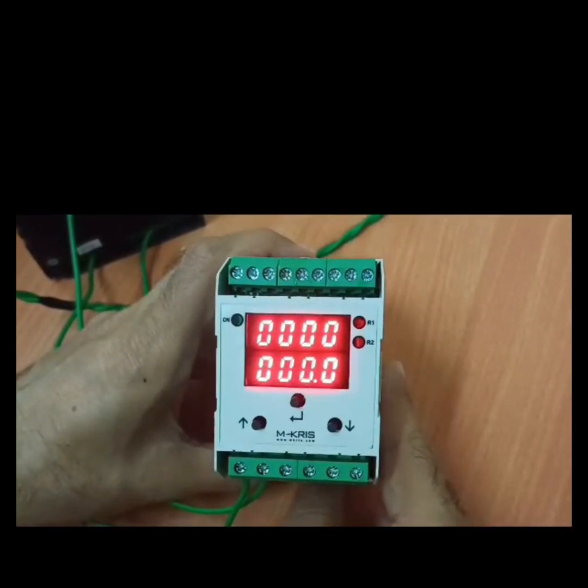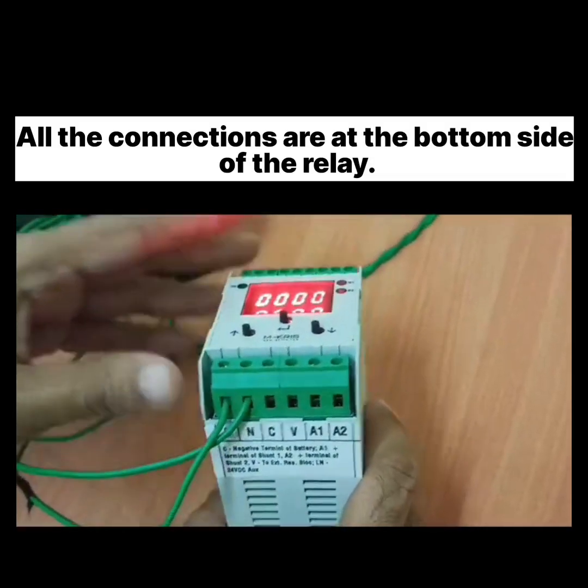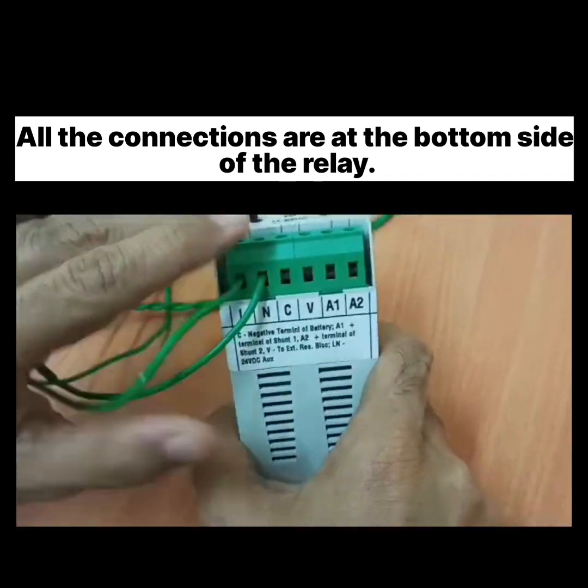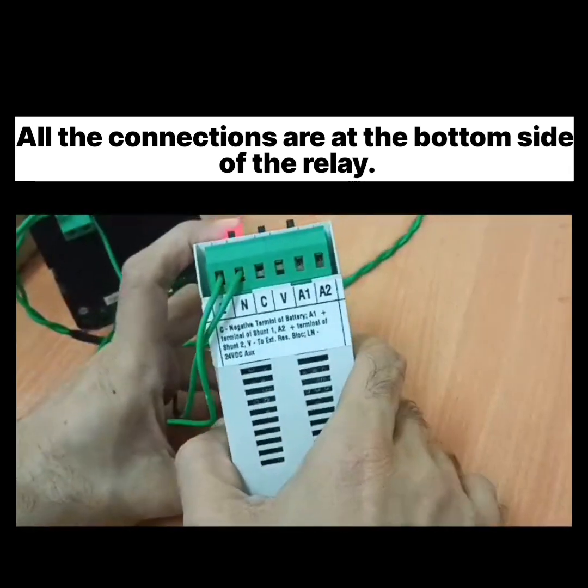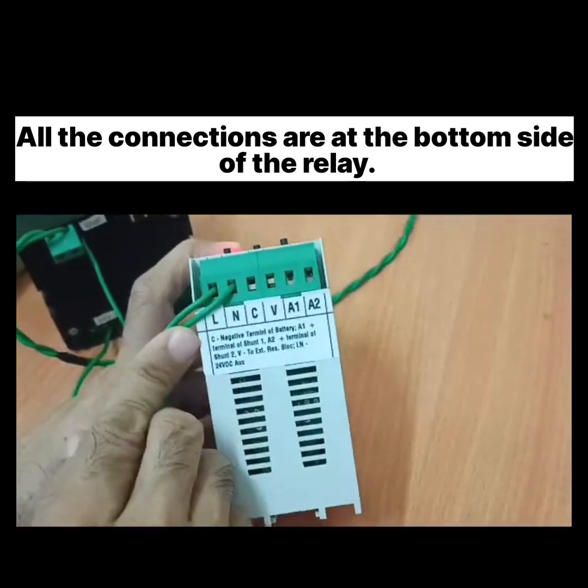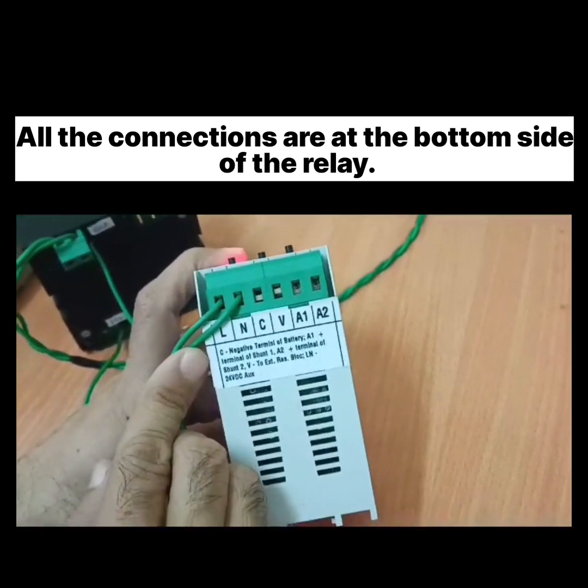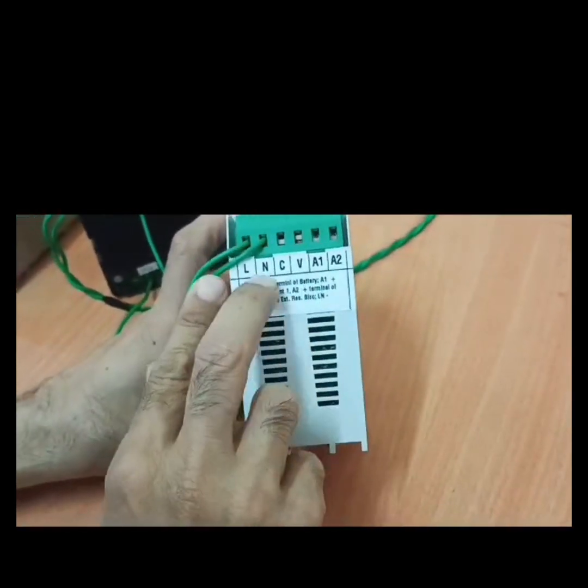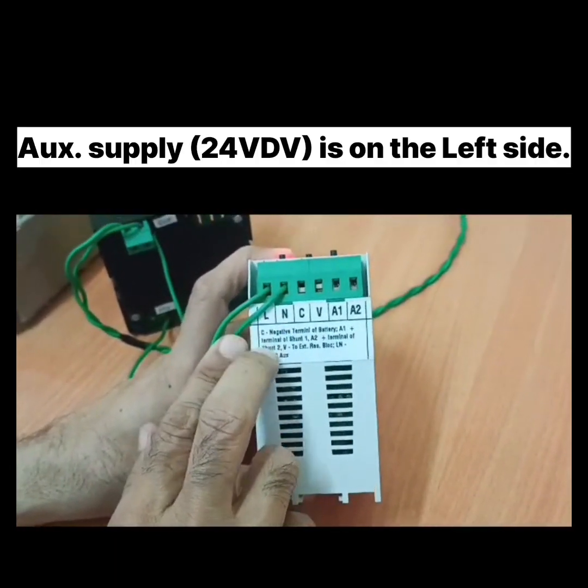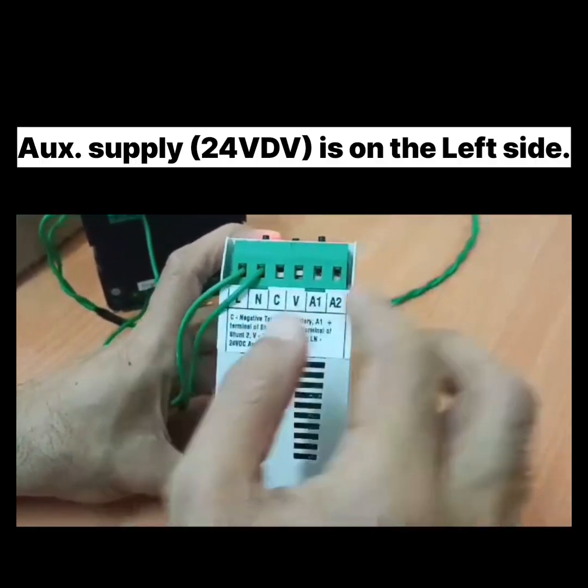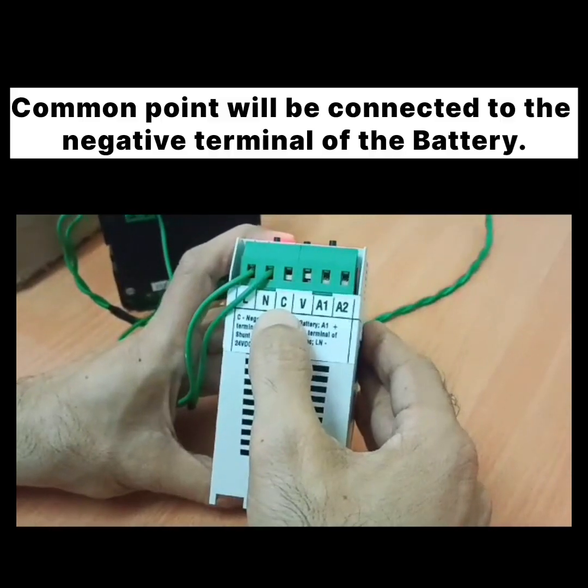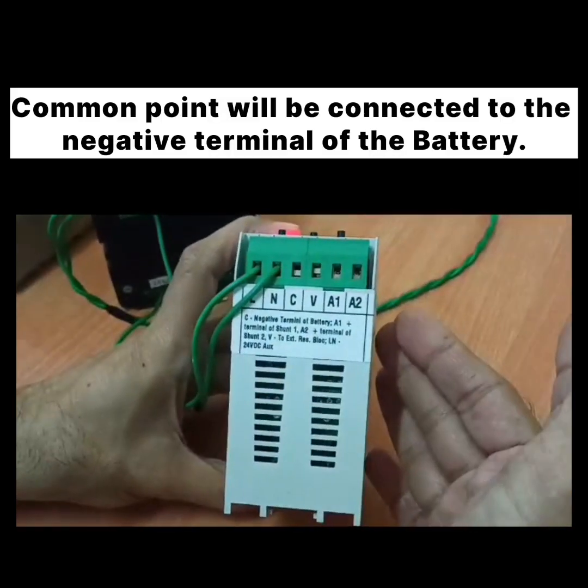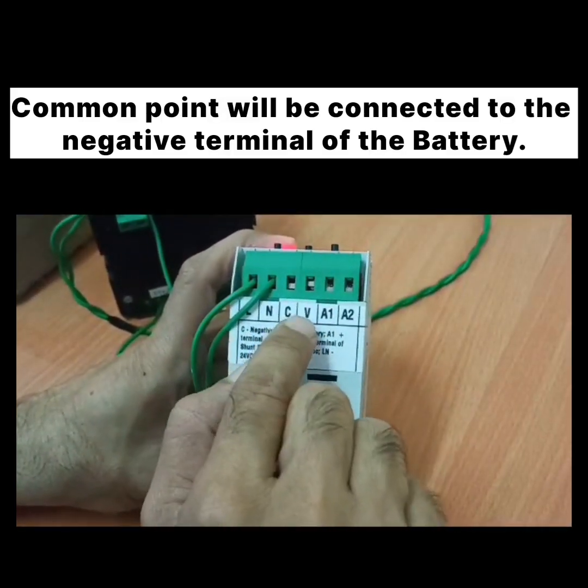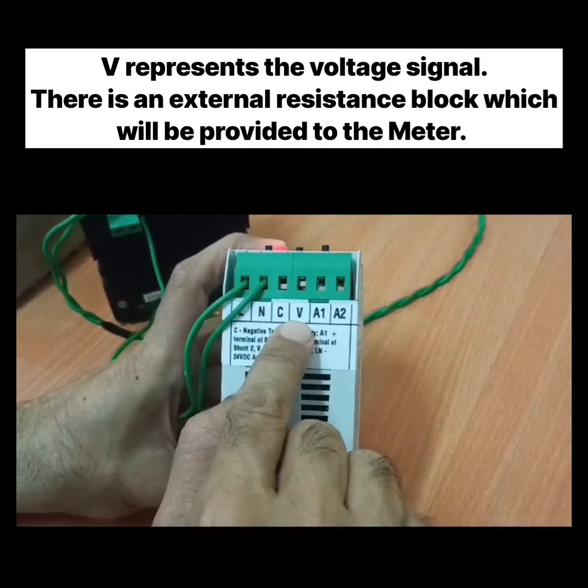Now we will have a look at the connections. All the connections are at the bottom, and the label gives the detail of how the connections are to be made. So auxiliary is on the left side. Auxiliary is 24 volt DC. Then this is the common point which will be connected to the negative terminal of the battery. V represents the voltage signal.